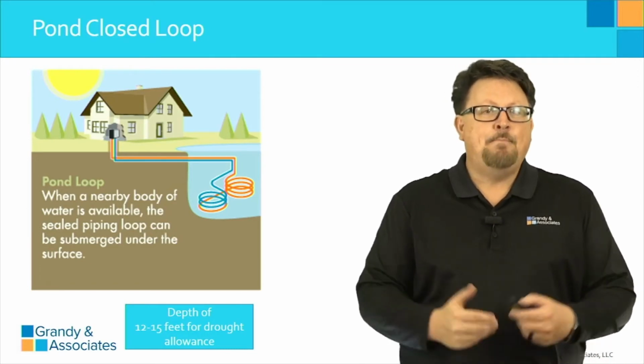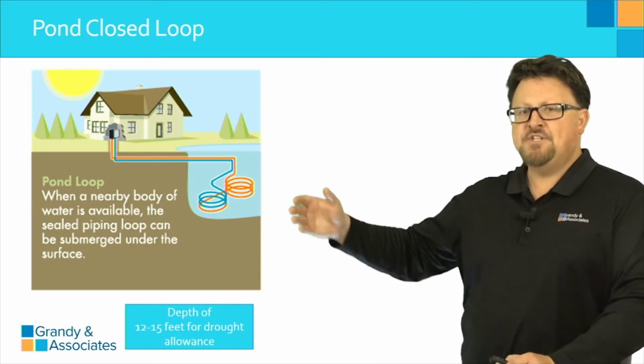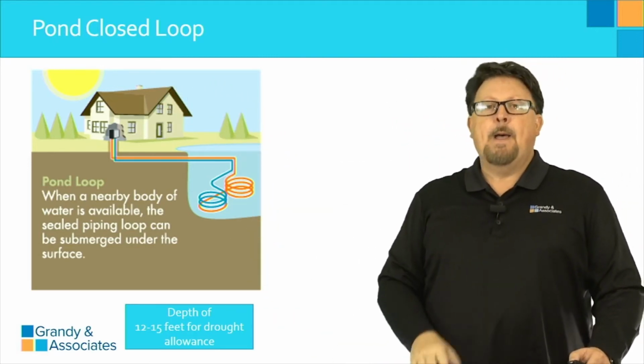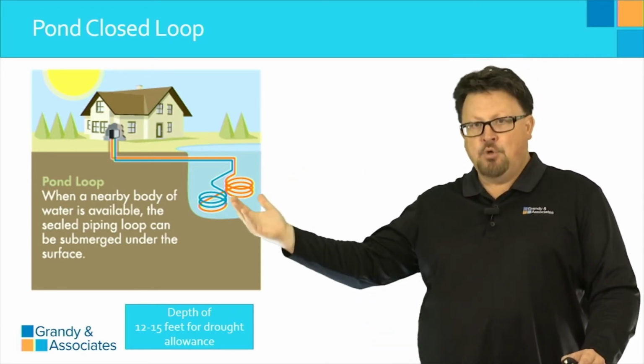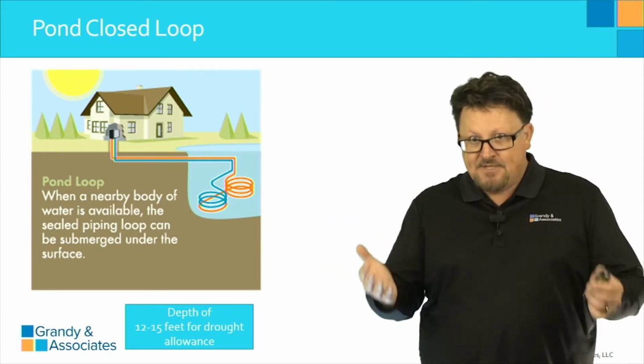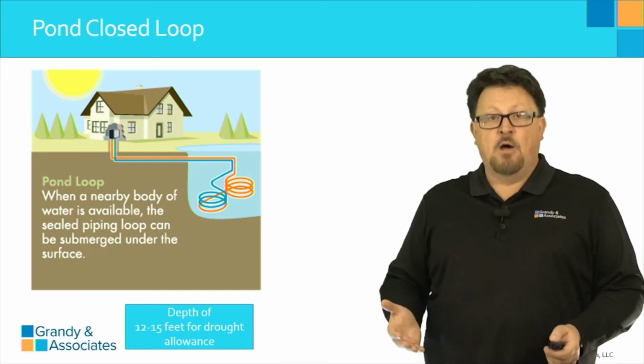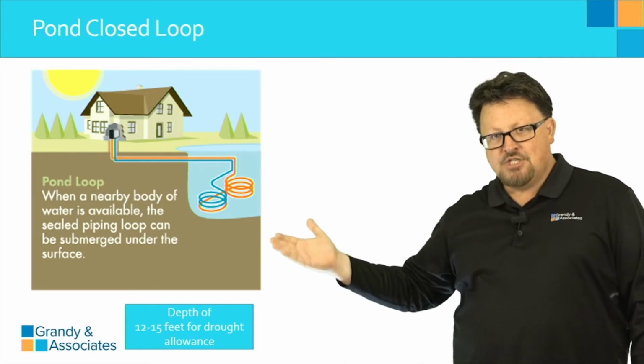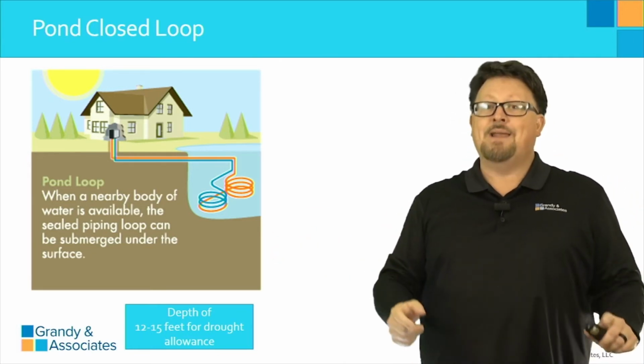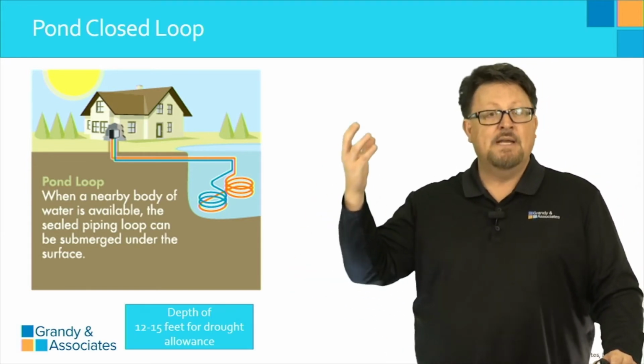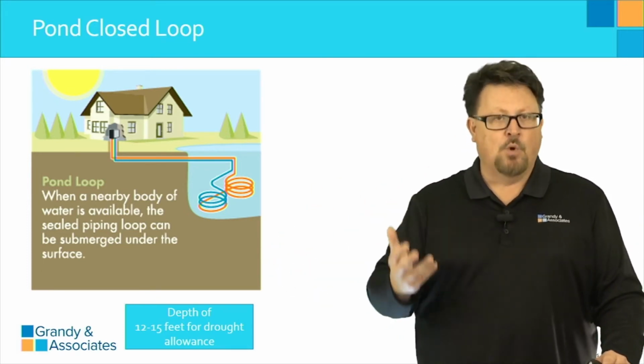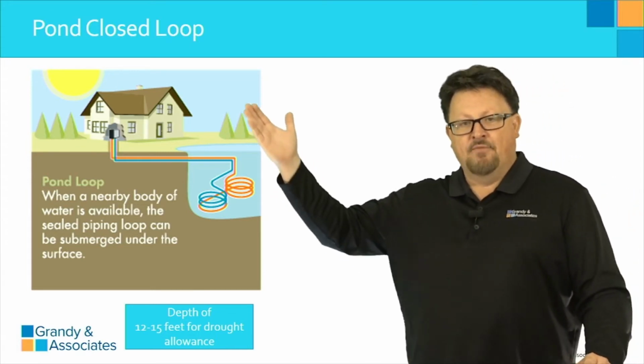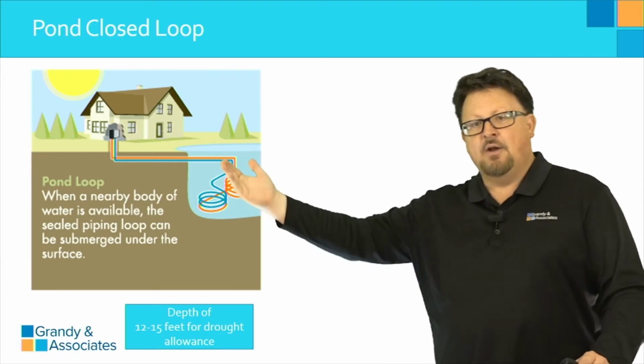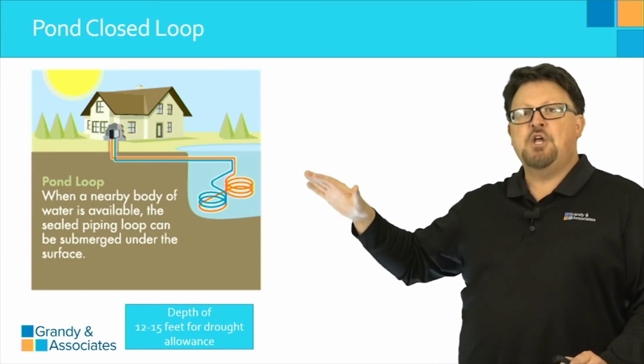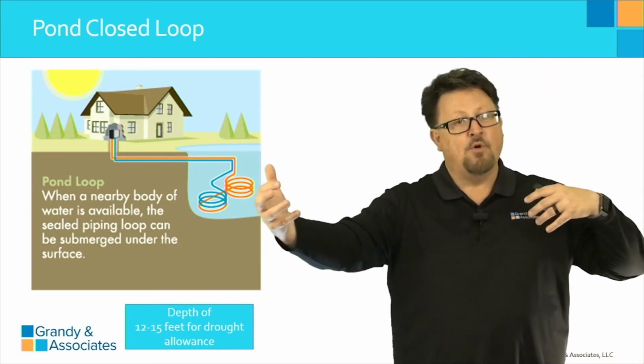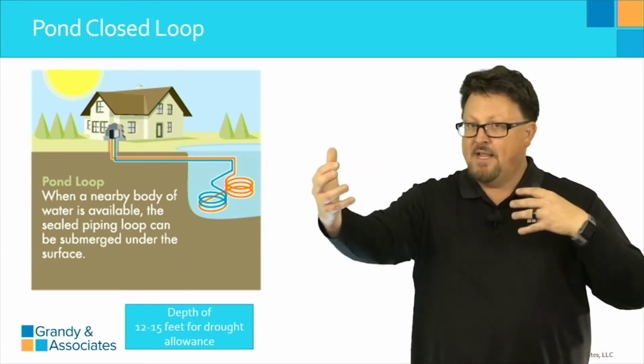The third type of loop is a pond loop or a lake loop. Now notice this is still listed as a closed loop, because most public lakes will not allow you to pull from a live source in a public setting. Maybe some will, but a lot of them will not let you do that. Many will allow you to put a closed loop submerged in the lake. You always verify that, because market to market it can be different—never assume. Your local Corps of Engineers, your codes department, can give you guidance on what's accepted where you live. But where allowed, this would be an example of a pond or lake loop, where a grid like you see here is taken offshore and submerged so you're able to have that conduction with the water, because water is a great conductor. So it helps enhance that exchange.